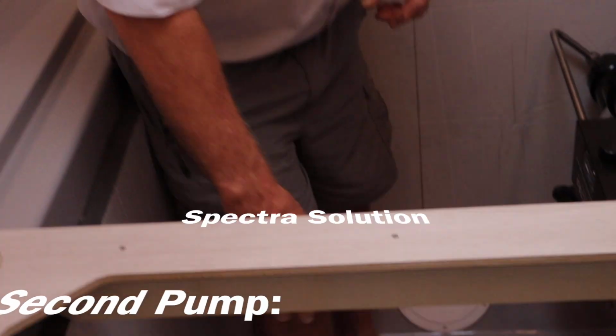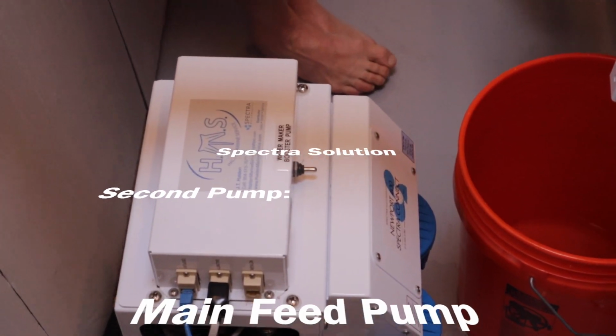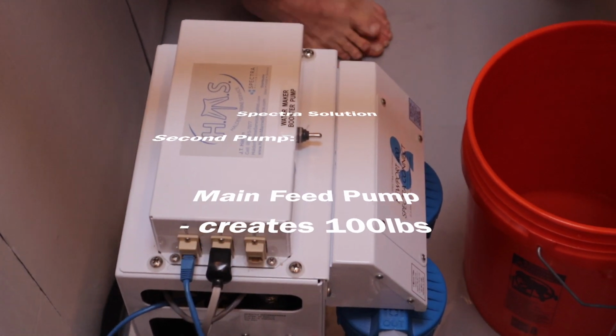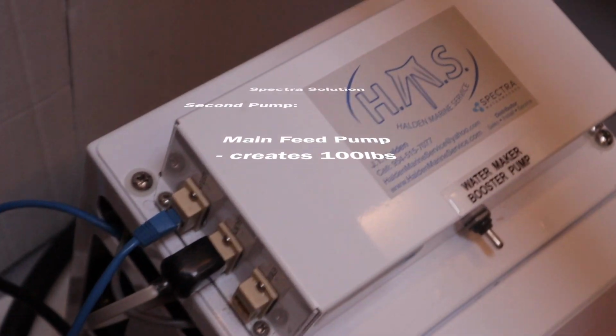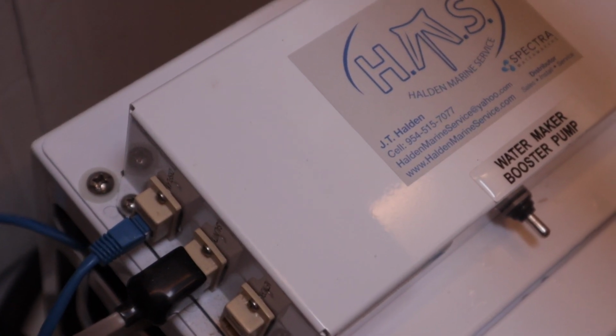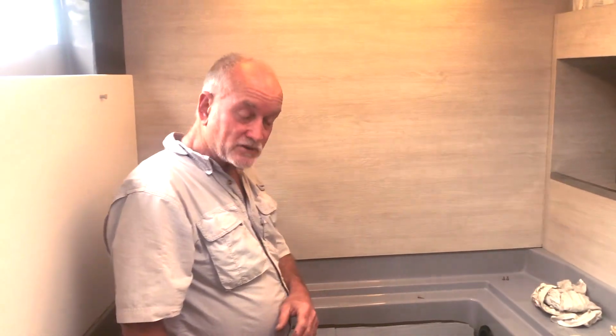This is our second pump. It's our feed pump. It's what we call our feed pump module. That white box. Inside there is the electrical motor and pump. It's going to start creating the pressure, and that's going to take about 10 to 13 pounds of pressure from the boost pump, and on a 400, it's going to boost it from about 80 to 120 pounds of pressure. So instead of creating 800 pounds of pressure, let's just use 100 pounds, as an average. So we're feeding this about 100 pounds of pressure from the feed pump, not 800 pounds.